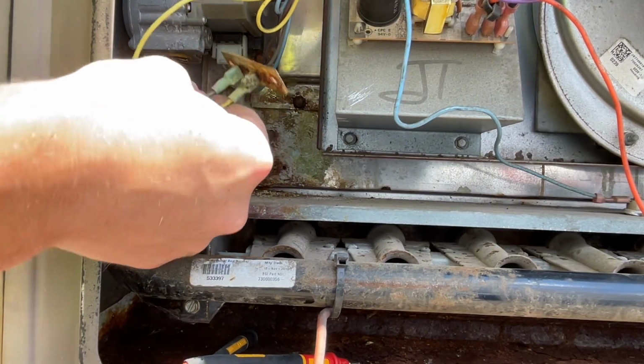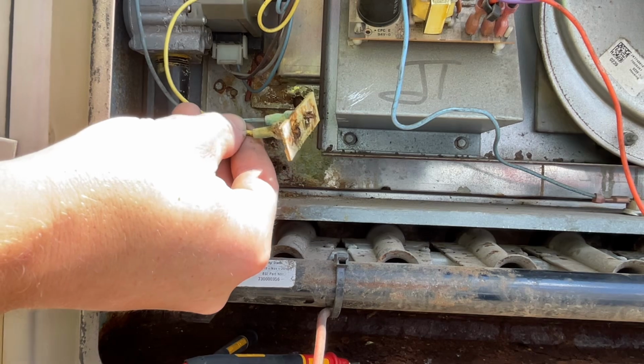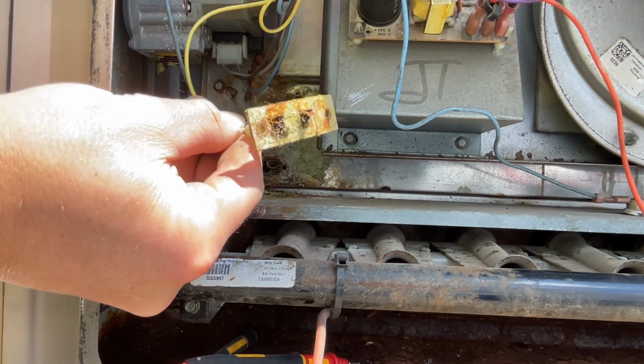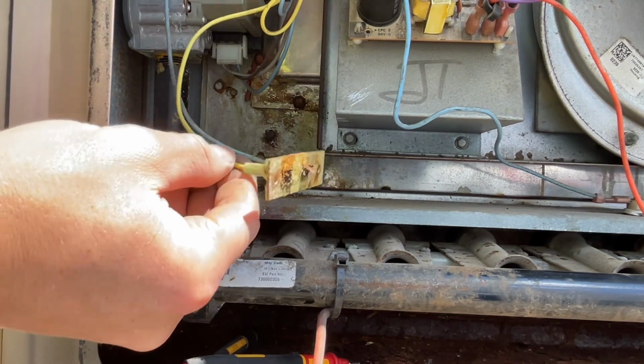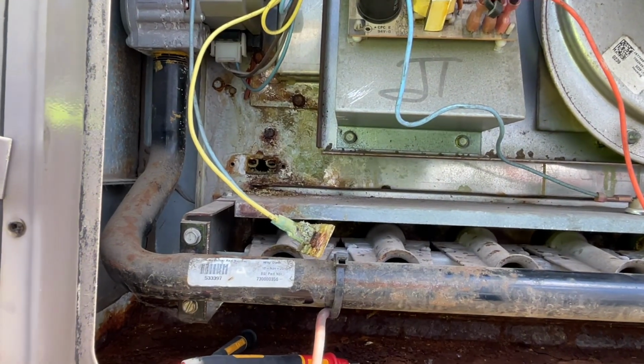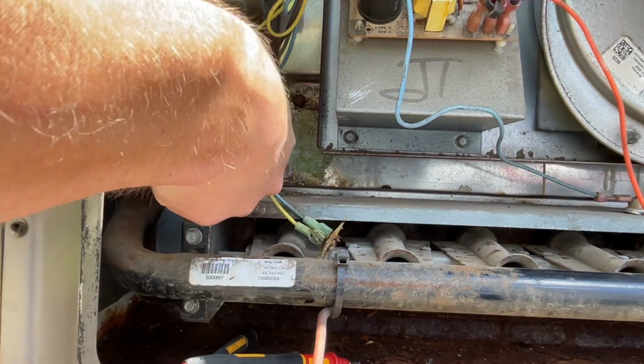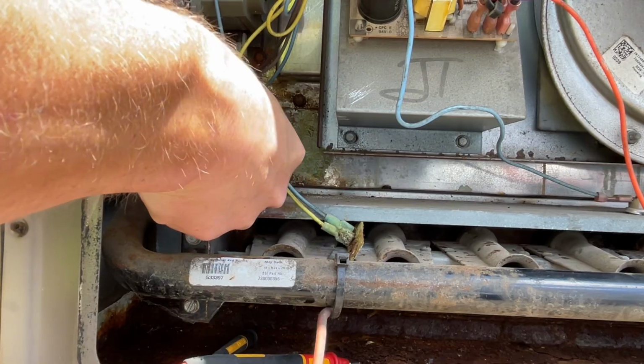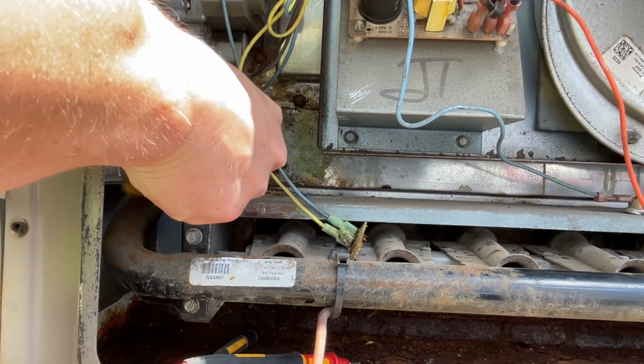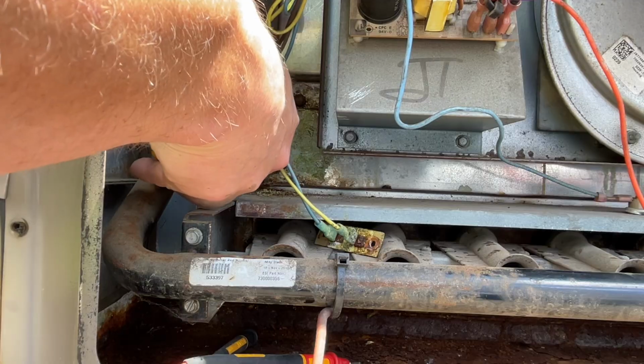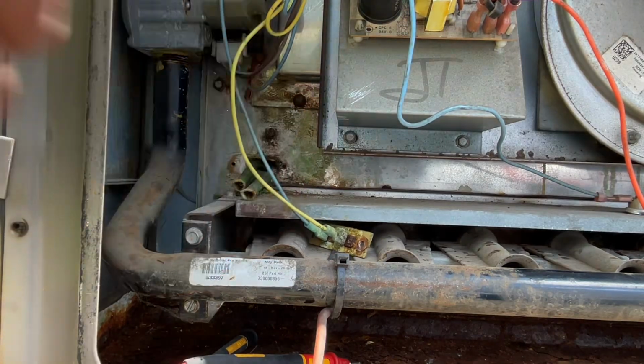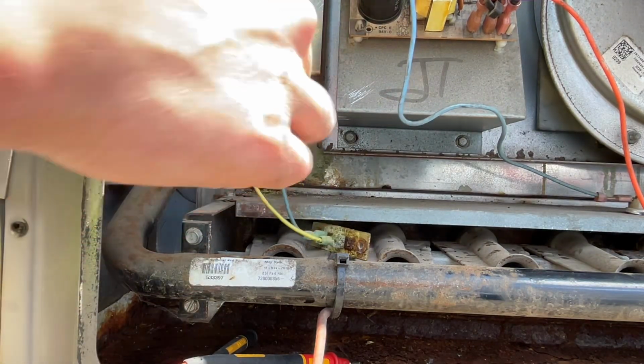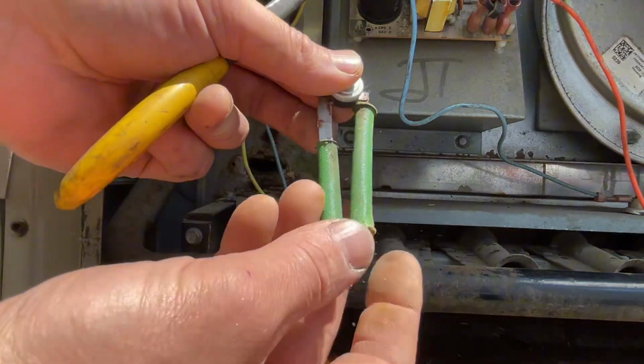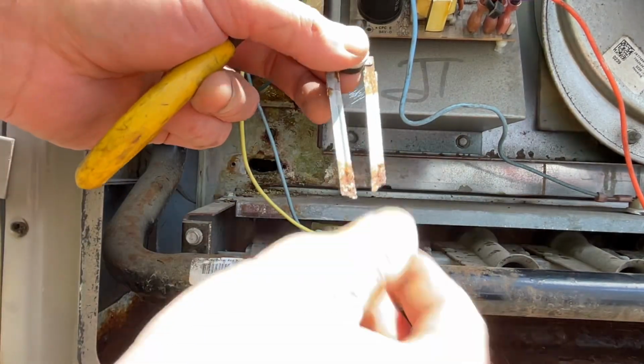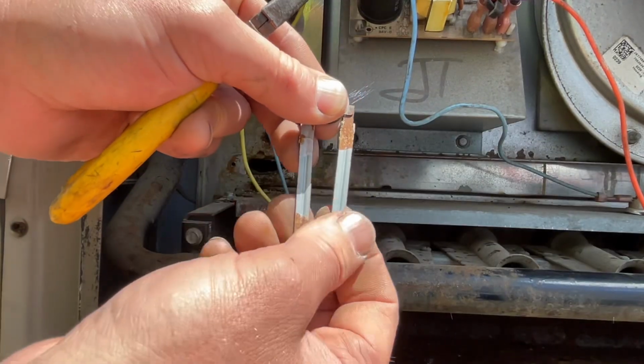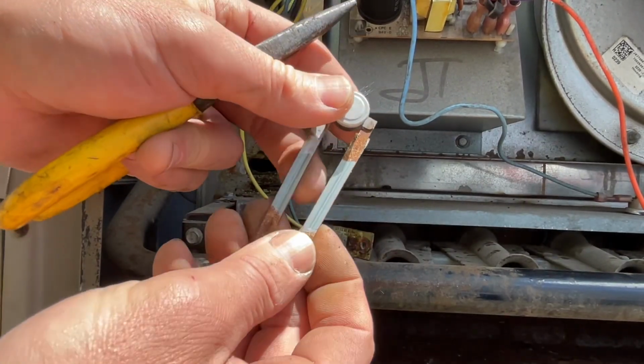Okay, there's our problem right there, guys. So the actual thermal disc on the other side of this, I'll see if I can pull it out and show you, has snapped clean off. I haven't seen one of these snap off in a while. Look at this here. We got to be careful because this has to come out and we'll have to order a new one. There it is. There's the other half of our high limit. So there it is there. So what has happened now is that these have become so corroded that they've just snapped right off.